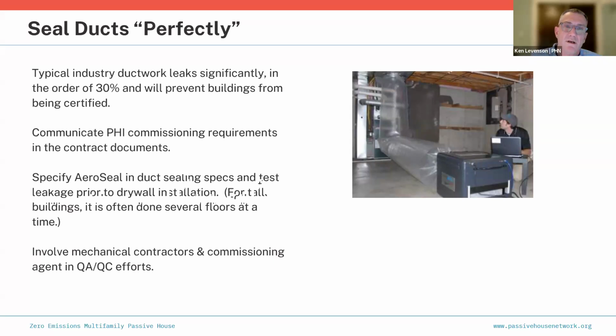So we're looking at the specification, making sure that they're on board. And then ultimately, if the project allows, on day one, backstopping that with aerosol air sealing. So AeroSeal, I'm waiting for somebody to tell me that there's another product out there that can do this. But until I hear it, it's the AeroSeal duct sealing. And so you see on the right in the picture, they are sealing and testing the duct. And you'll know at the end of the day that you actually have ducts that are tight enough that you can balance and commission the system and hit the numbers that you need to be certified and deliver the results.